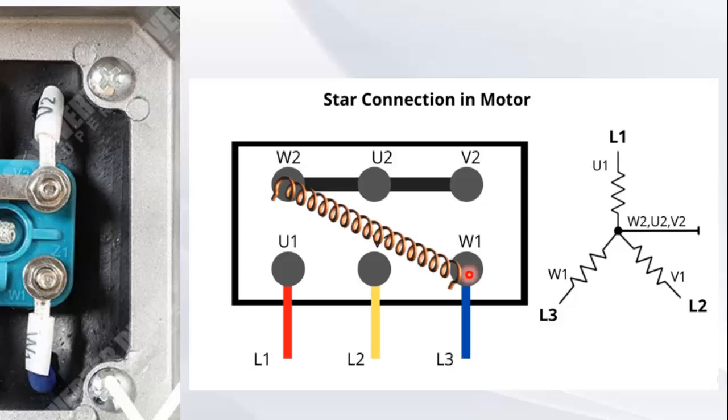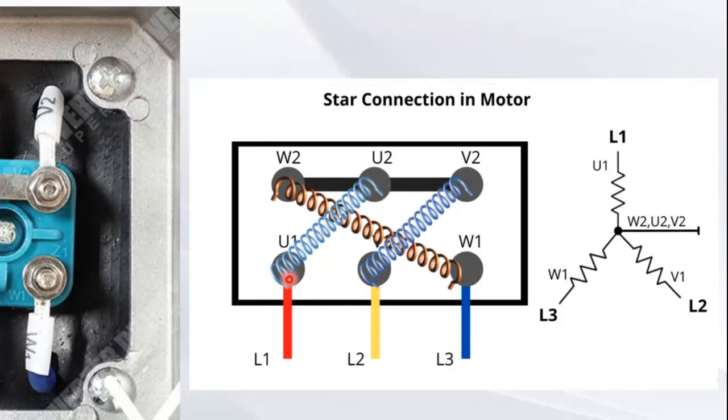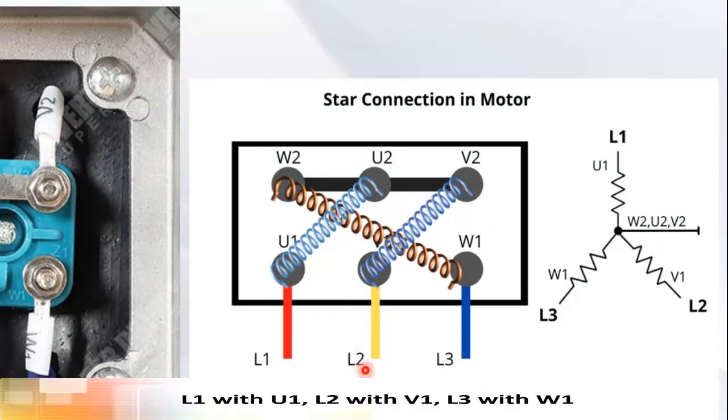Let's draw the winding so you can understand how the actual windings are connected. For star connection, short W2, U2, V2 together and connect L1 with U1, L2 with V1, and L3 with W1.